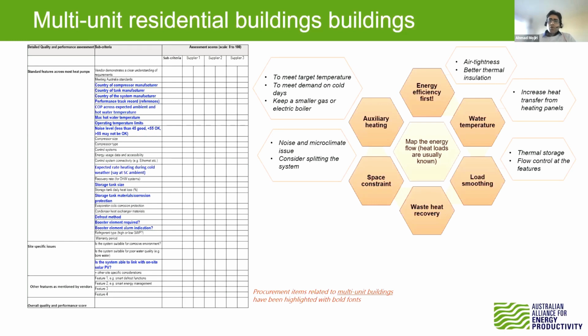The second important design consideration is the water temperature. Most of the time, the supplied water temperature has been selected according to, for example, a hydronic heating system requiring 80 degrees C. But we know that with improvement of the heat transfer rate from those heating elements in the building, we can run the entire system at a lower temperature. So that needs to be revisited, and by increasing the heat transfer of those panels, we reduce the required temperature and enable more heat pump options to deliver the heat.